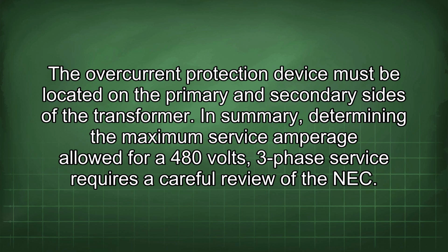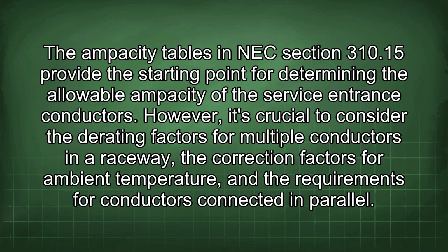In summary, determining the maximum service amperage allowed for a 480 volts, three-phase service requires a careful review of the NEC. The ampacity tables in NEC Section 310.15 provide the starting point for determining the allowable ampacity of the service entrance conductors. However, it's crucial to consider the derating factors for multiple conductors in a raceway, the correction factors for ambient temperature, and the requirements for conductors connected in parallel.